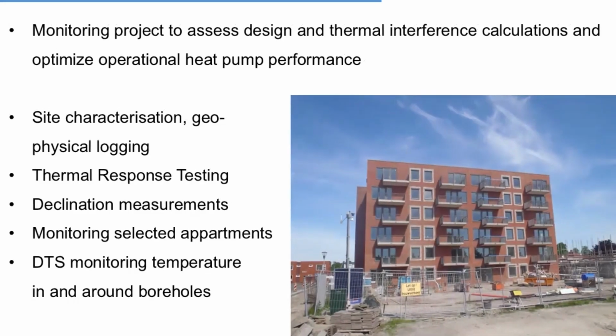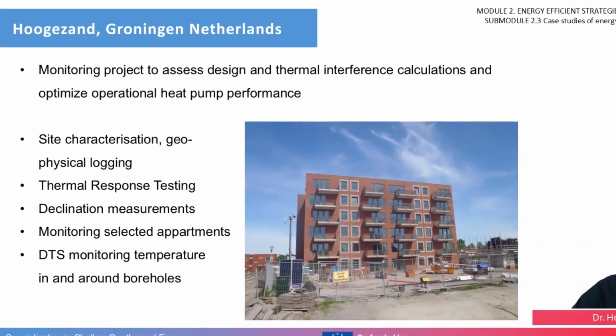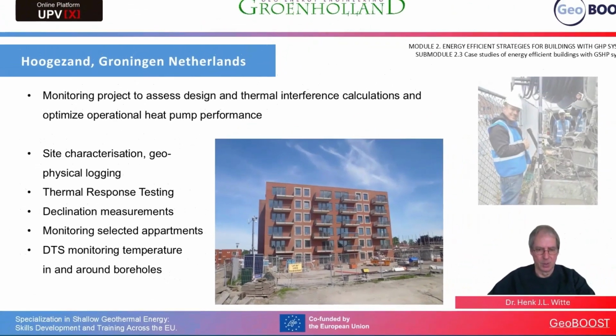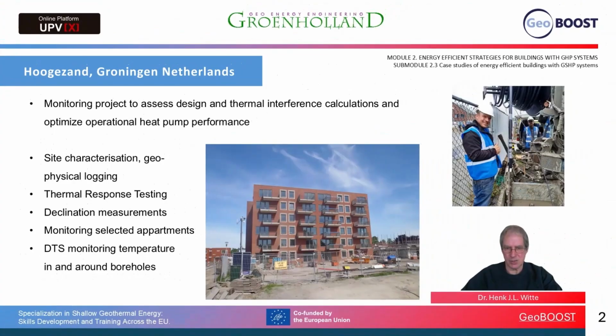We then selected a number of apartments for the monitoring. 3 apartments were monitored in detail, both the apartments themselves, but also the boreholes connected to those apartments, with distributed temperature sensing using fiber optic cables installed across the whole length of the borehole. And we had additional boreholes drilled at small distances from the borehole heat exchangers to measure the temperature evolution in the ground at different distances from the actual borehole heat exchangers.